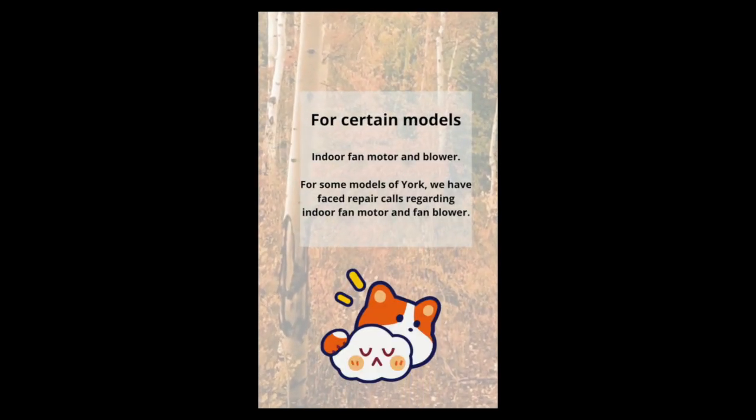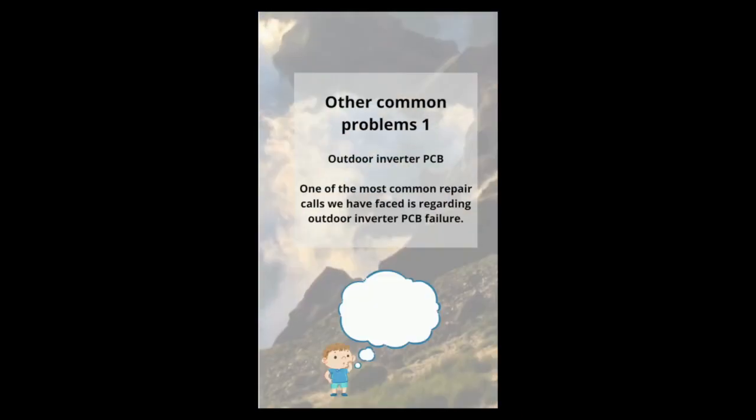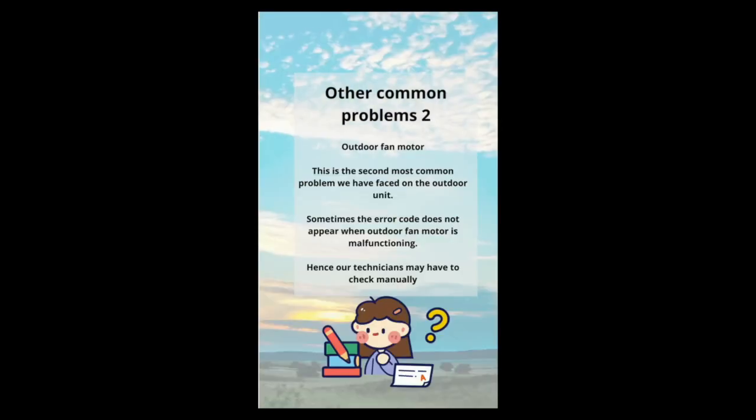For certain models, one of the common problems we have faced with York aircon is the indoor fan motor and blower. Another common problem is the outdoor inverter PCB. The second most common problem on the outdoor unit is outdoor fan motor malfunctioning, and sometimes the error code does not appear when the outdoor fan motor is malfunctioning.